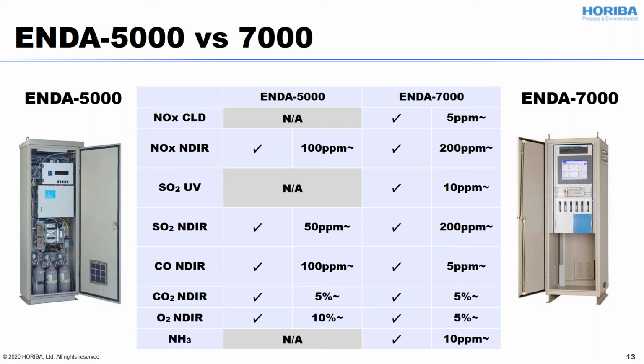Okay, let's see. So ENDA-7000 can do the 5 ppm analysis for NOx and the 10 ppm analysis for SO2, because of the chemiluminescence and the UV, and even NDIR, while ENDA-5000 can do the 100 ppm range for CO, but ENDA-7000 can do the 5 ppm CO.